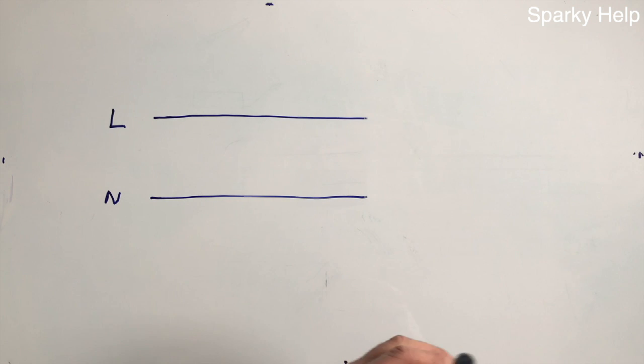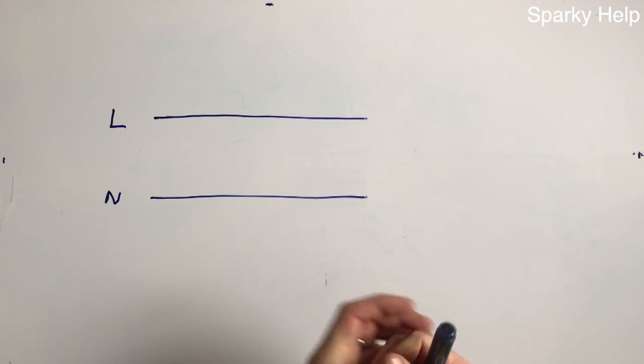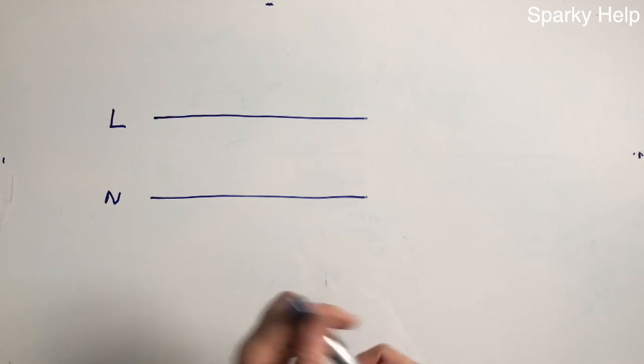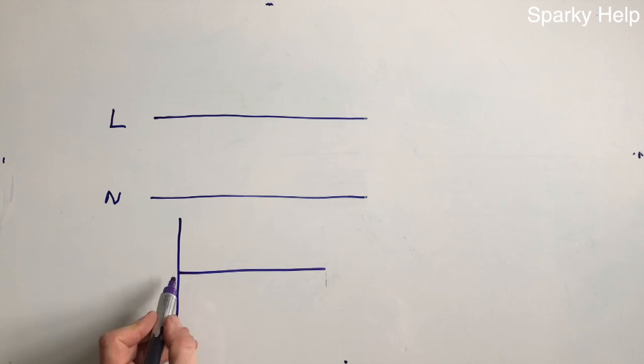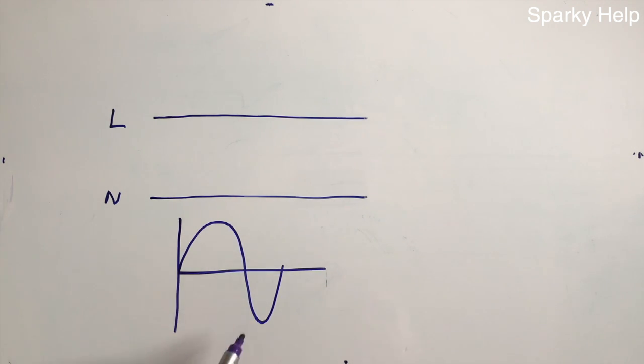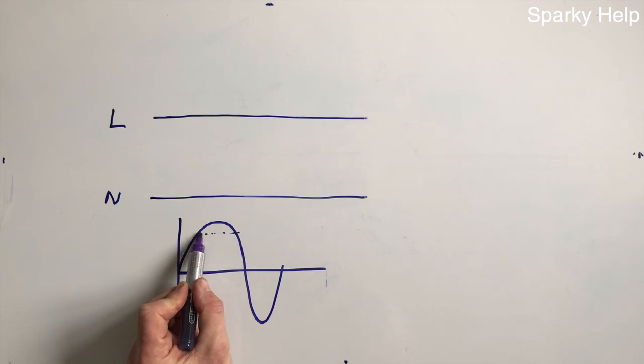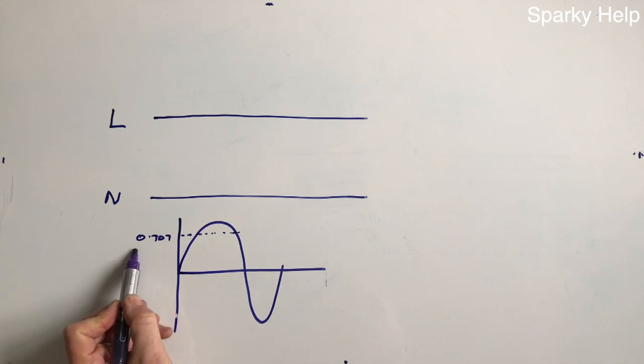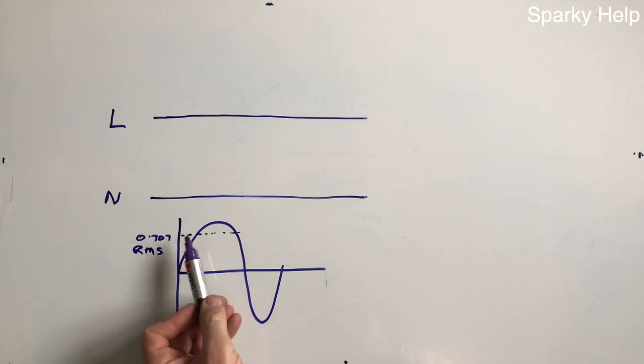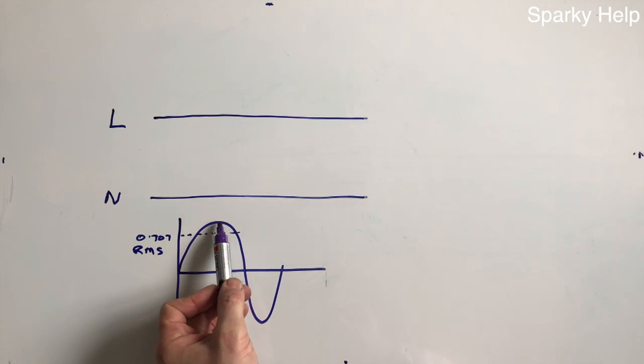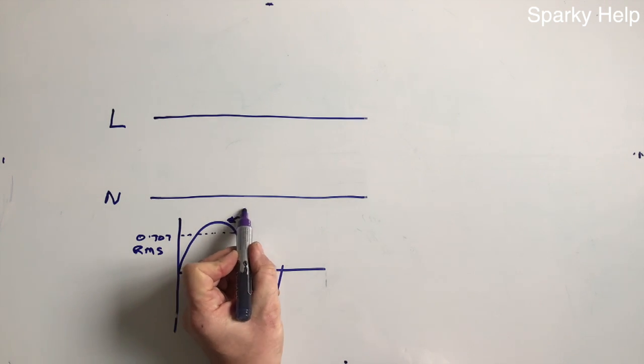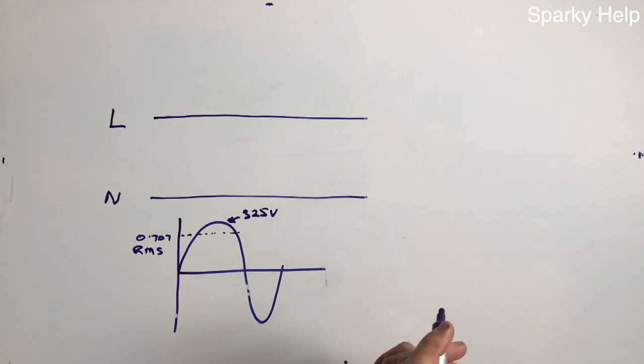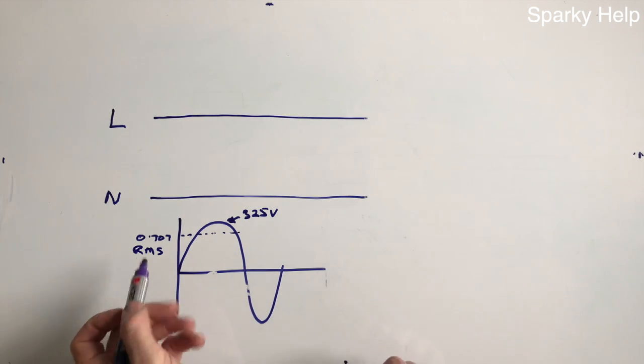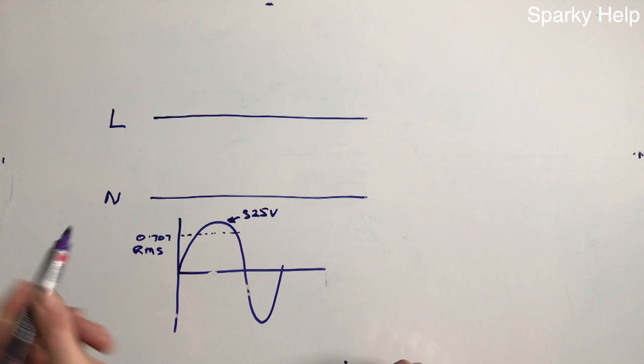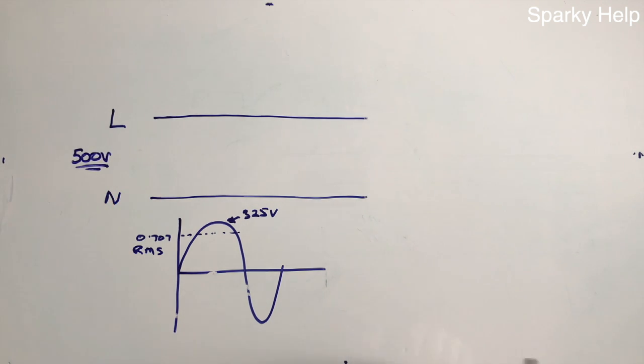Well, it comes back to the fact that 230 volts is an RMS voltage, and RMS is 0.707 of the sine wave. In other words, just to give you a rough idea, there's our sine wave, very badly drawn, very uneven, and our 230 volts is roughly there, 0.707, which is called, and you've probably heard it before, the RMS. So actually 230 volts is here, but actually goes up a lot higher. In fact, what it actually peaks at is roughly 325 volts, but it's there for such a small period. So 0.707 is the RMS, because it's the equivalent heating effect of a 230 volt DC supply. So therefore when we test it, we test at 500 volts, because that's higher than what goes in there.